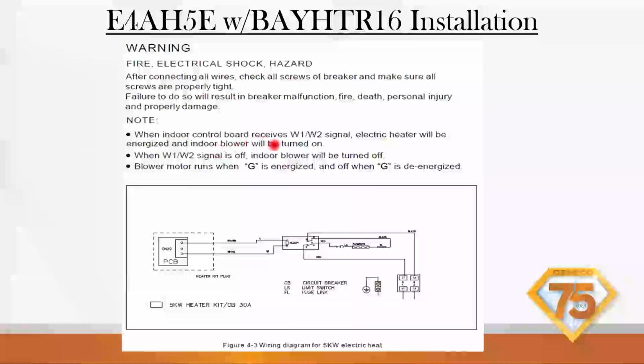When the indoor control board receives a W1, W2 signal, the electric heater will be energized and the indoor blower will be turned on. When the W1, W2 signal is off, the indoor blower will be turned off. Blower motor runs when G is energized and is off when de-energized. So green functions your indoor blower. Just going over what you're doing with the L1, L2.